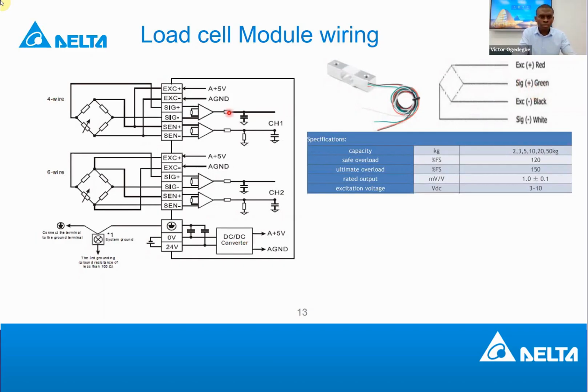Then the signal plus goes to this signal plus, and the signal minus, which is white in this case, goes to white as well. So this signal terminal is where the load that the sensor measures is given to the load cell module. And on the load cell module terminal, SEN, you have the sense plus and sense minus. So this terminal is there to compensate for impedance.